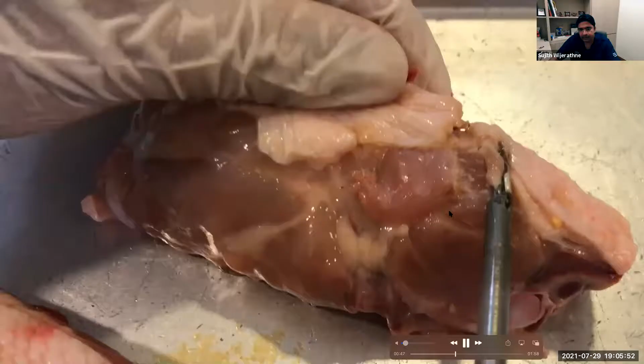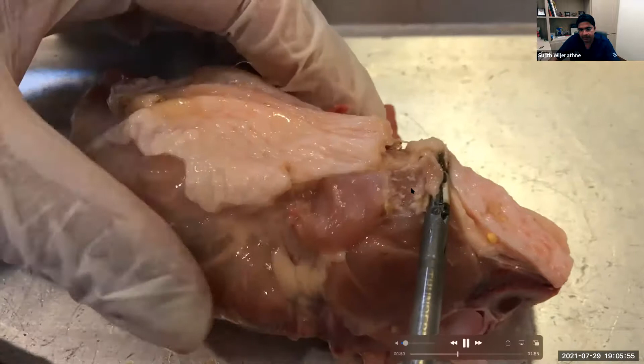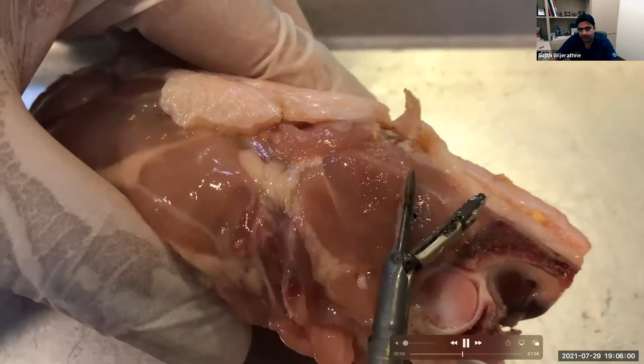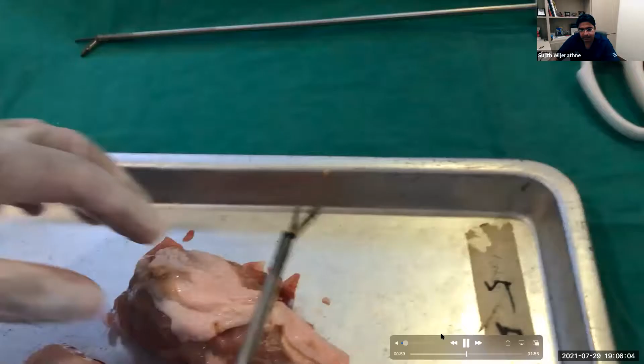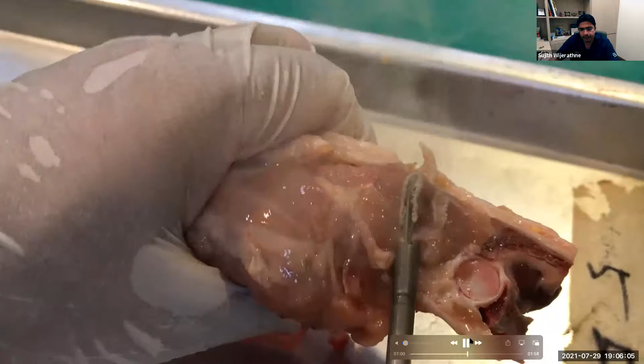If you need to cut and seal at the same time, we use the pink color button. You can see the tissue effect here. It does cause some lateral damage. It does produce some mist. This part is important. It produces the mist, and then you can see the amount of energy that it uses. This is without activating. You can see how much tissue damage can occur. This is due to the residual heat, and you can see the amount of lateral thermal damage.